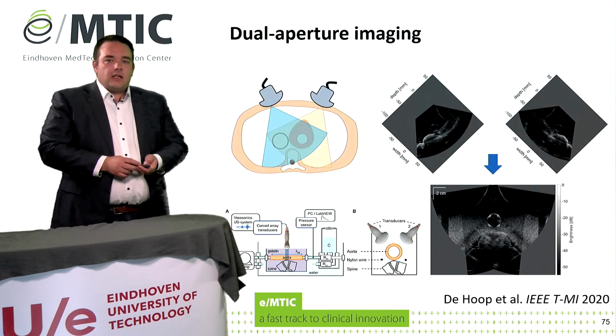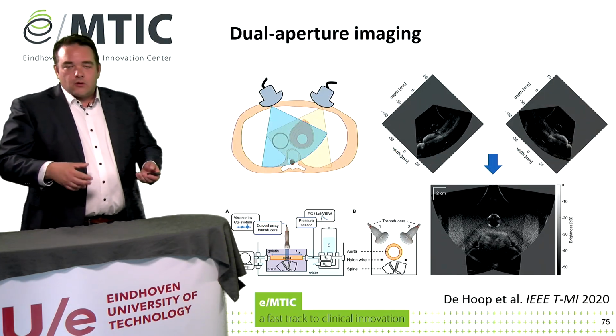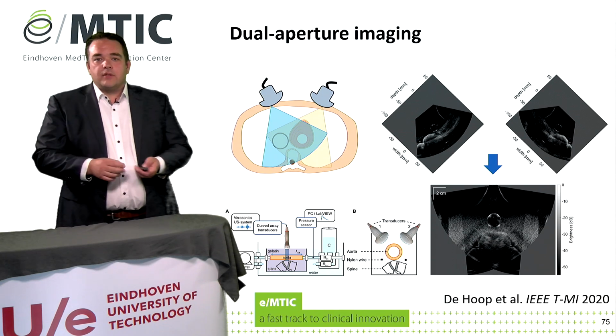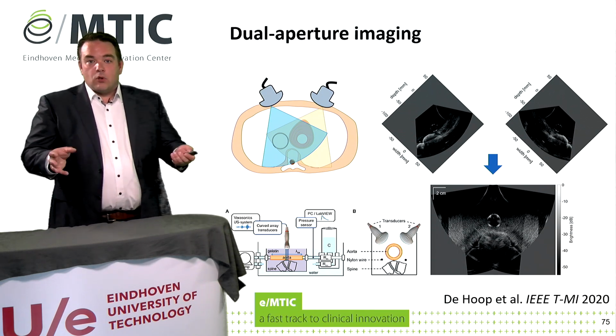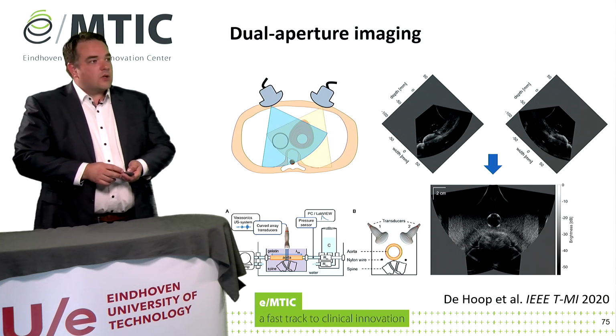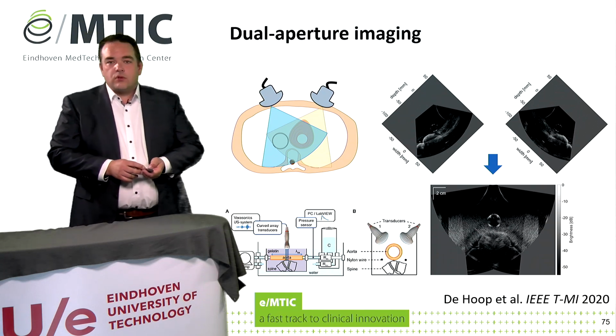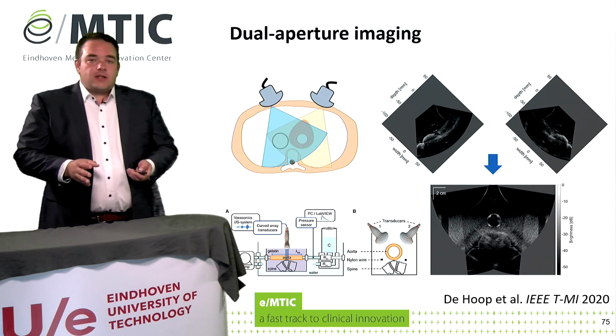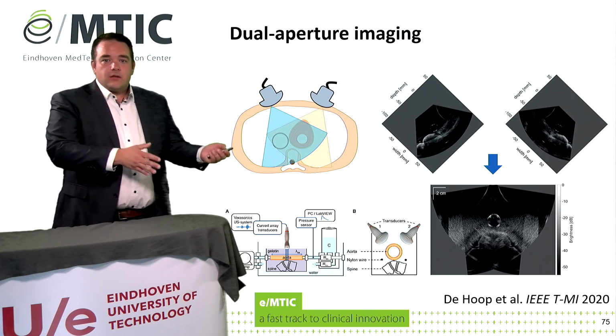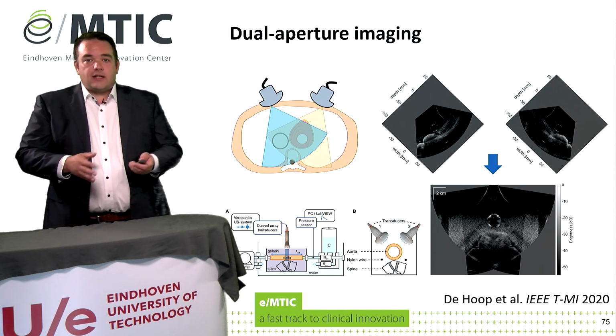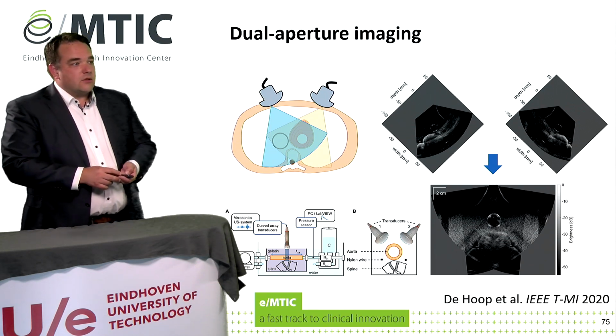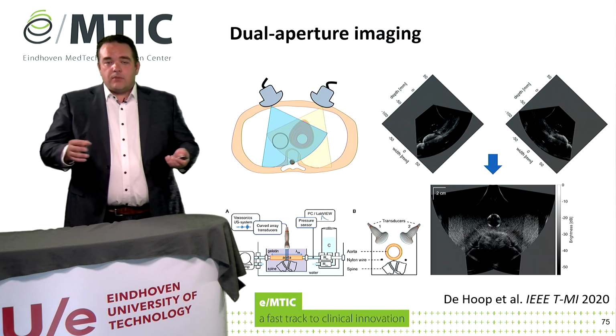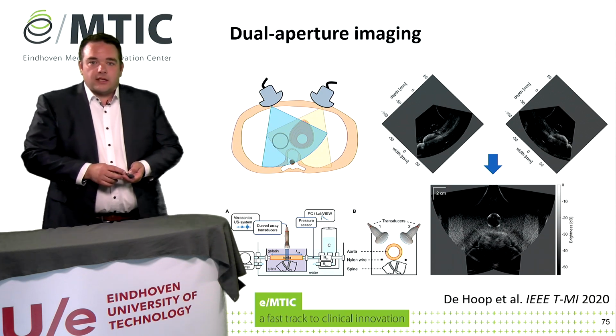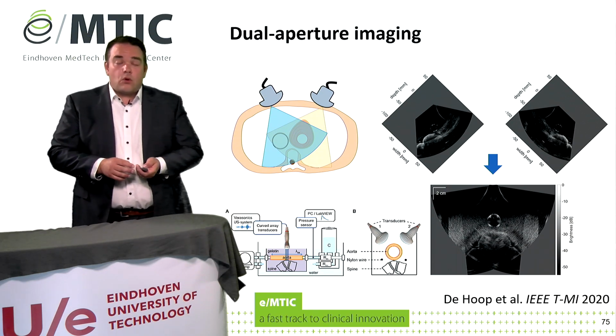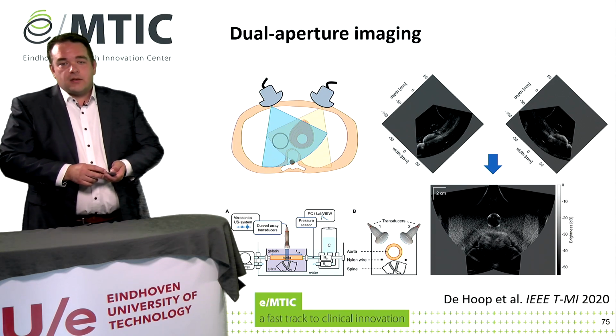But ultimately, what we want to do is not image an organ at different points in time from different positions, but have a multi-aperture system. This is one of our prototypes where we actually have 2 curved arrays that can operate in an interleaved fashion. So probe 1 creates an image, then probe 2, and then we can combine these data, as you can see in the combined image in the bottom, and you immediately see that the total aorta has a much more homogeneous appearance than in the single images.